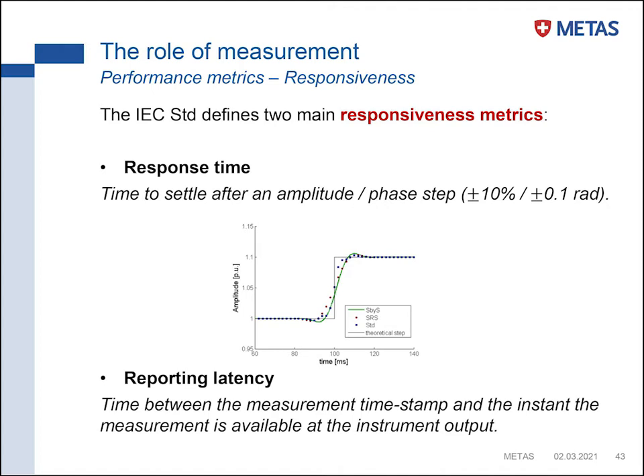Because what is important to say is that the PMU will give us some timestamp measurements, so then we can aggregate all the measurements and compare the measurement with the same timestamp. But we have to be sure that the measurement is available at the output of the instrument as fast as possible, because we have seen that the control action has to be taken in the order of seconds. So we cannot wait for the packet too much time. We have to be as fast as possible.